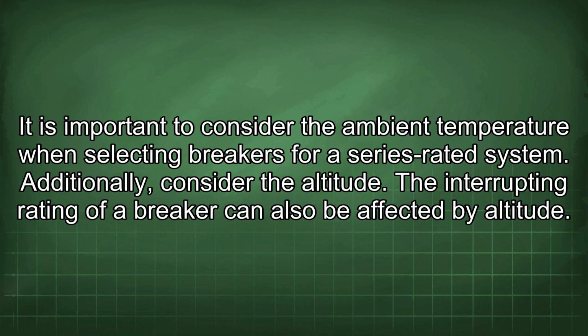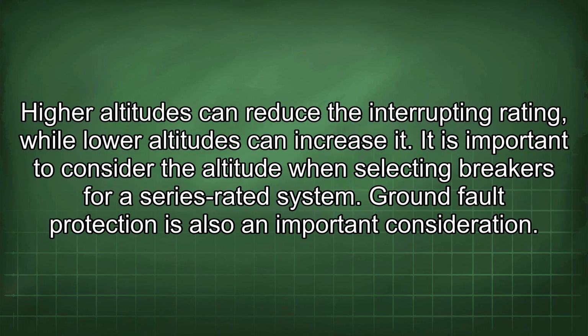Additionally, consider the altitude. The interrupting rating of a breaker can also be affected by altitude. Higher altitudes can reduce the interrupting rating, while lower altitudes can increase it. It is important to consider the altitude when selecting breakers for a series-rated system.